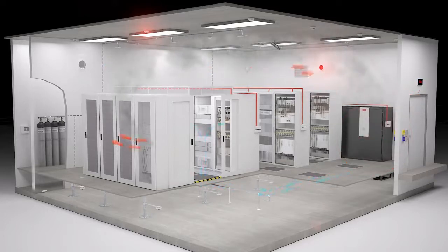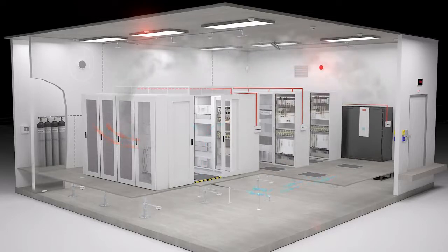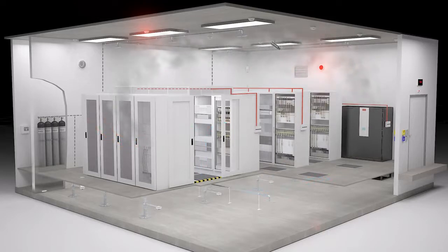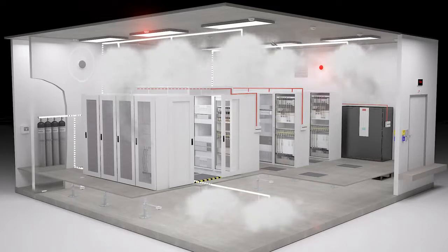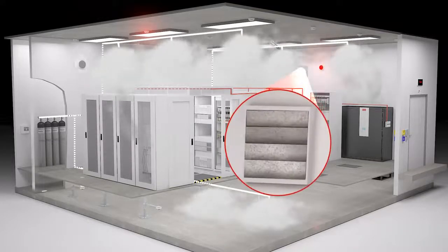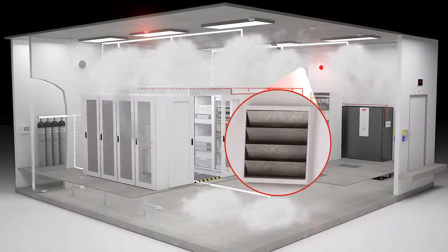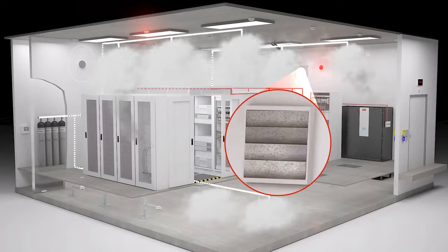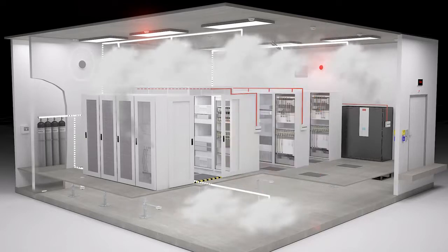After the defined operational delay time has elapsed, the flooding of the Sinorix CDT extinguishing system begins. As the flooding begins, the overpressure flaps open to ensure the structural integrity of the room.